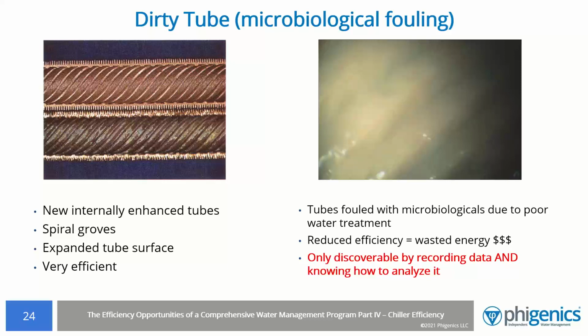The tubes you're looking at on the left side, at the very top, is a cutout view of a clean tube. Below that is an internally enhanced tube that's got microbiological fouling. If you look at the slide on the right, this is a reading that we took to get an idea what was in the tubes, and you can see the grooves in the tube. You can see the microbiological scale, slime. This resulted in a very significant energy efficiency loss on that chiller.